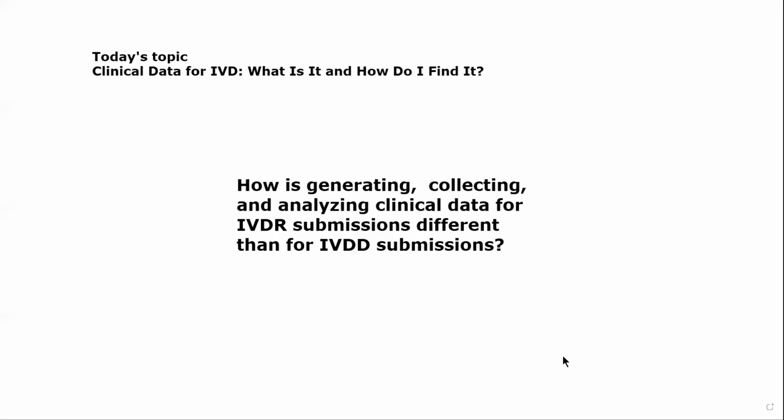You establish the association, you provide information regarding your purpose and things like that. But clinical data is a brand new requirement, particularly how it relates to risk. So that's going to be the primary difference that I would propose: it's going to come down to how we are collecting data for real world scenarios, real world usage of our device in clinical settings.